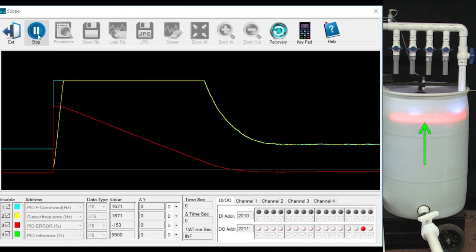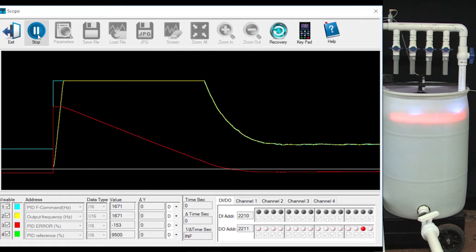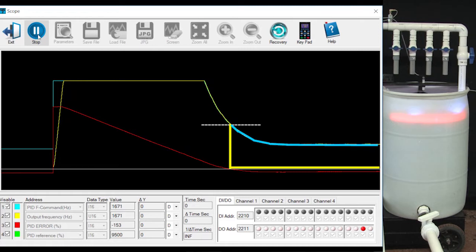Well, that's where sleep mode comes in handy. Sleep mode 2 monitors the PID command frequency, the blue line on our chart here, and when it sees it slow down enough, it disconnects the blue PID command frequency from the yellow output frequency which turns the motor off.